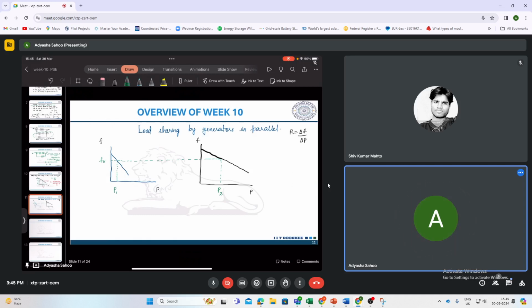So basically, there will be an increase in the output of both the generators to meet the increased load demand. So let's say the new outputs are P1 dash and P2 dash, and the new system frequency is F. So what is the change in output of generator 1? It is P1 dash minus P1. And how much was the change in output of generator 2? It was P2 dash minus P2. And this delta P1 plus delta P2 is your change in load, delta PL, which I was telling is 100.